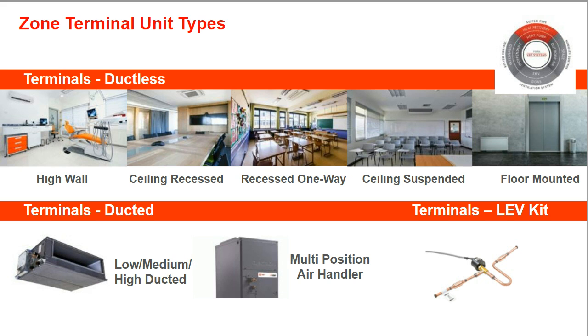There's also the option to use linear expansion valve kits, or LEV kits. These refrigerant modulating devices can be useful to incorporate advanced air handler unit options, as well as benefiting from long line runs for split air handler units. These LEV kit air handler unit combinations can be used to serve spaces such as large auditoriums, large open office spaces, or to add a dedicated outside air system to the VRF system.